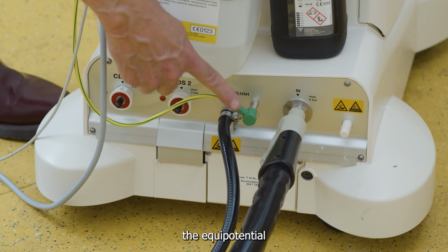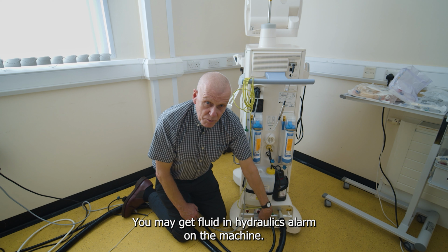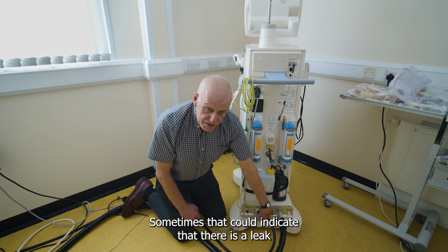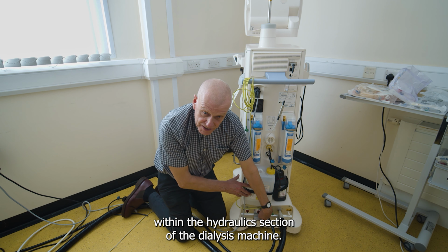You may get a fluid in hydraulics alarm on the machine sometimes. That could indicate that there is a leak within the hydraulic section of the dialysis machine. And that is shown by this little pot on the back here, filling up with fluid. There's a leak sensor in there that will give the alarm. However, often we have had problems in the past with bags of saline that have leaked at the top of the machine.